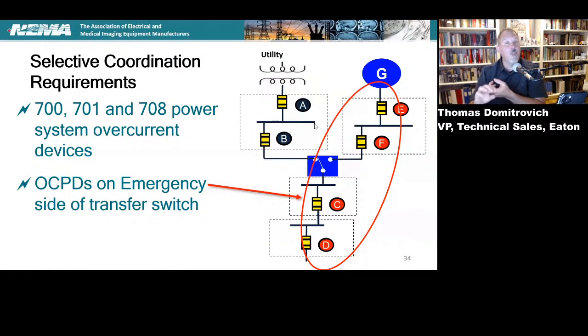What you don't know is what happens on a ground fault, which is one of the most common faults in a power distribution system. You don't know what happens on an arcing fault, which is another common problem in the system. And you don't know, obviously, what's going to happen in a three-phase bolted fault. But in a 700 and a 701 and 708 system, and also in data centers, these are the life safety systems, and data centers. I guess if my bank shuts down, that's life safety for me, right? I can't go shopping. But in any case, in those scenarios, they're requiring you to do an evaluation of all of these devices with regard to the amount of fault current that they will see. And they've elected to pick the three-phase bolted fault current as the level of fault current that you need to coordinate to or selectively coordinate to, because you're not going to see anything higher.